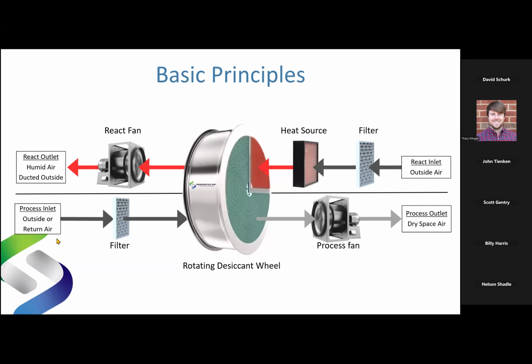Okay? I take this wet air that I want to process and dehumidify through a filter of some type. Our units can accept MERV 8s up through MERV 16s. On the inlet side, we can do HEPA and ULPA filtration on the discharge side, should you want it. I then may run it through a pre-cooling coil, depending, but sometimes not. And this warm, humid air, filled with moisture at a high grains per pound level, flows through these flutes and comes in contact with the silica gel material, which has been embossed into the substrate material. The silica gel, because it's dry, is at a very low vapor pressure. And just like the silica gel in the box, it is able to adsorb, or suck, the moisture out of the air in this high moisture level airstream coming in and hold that moisture as a water molecule in the pores of the silica gel, never condensing, never getting wet. The wheel is always dry.